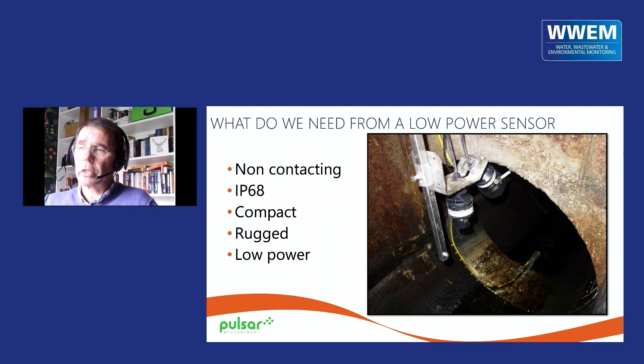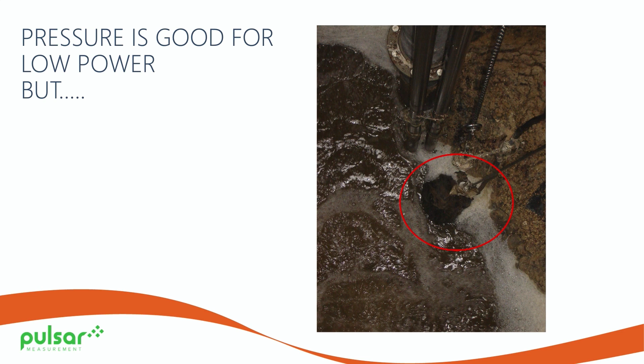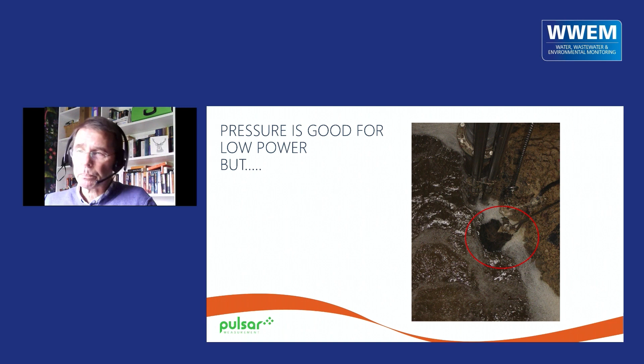So why are there low power devices out there? People ask me, why can't we use pressure transmitters? Well, we can, and they're good for clean water, but this is a picture I took years ago, replacing a pressure transmitter in a wastewater lift station. That circle there is the pressure transmitter, probably 5 or 6 times bigger than it used to be, full of rag and debris. So in wastewater applications, non-contacting is the way to go. And if you can reduce the power too, that's a win-win situation.